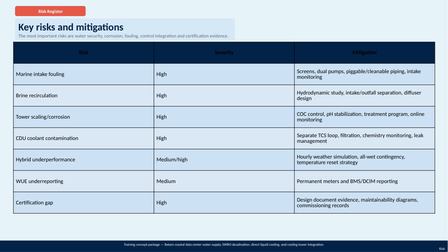The risk of coolant contamination in the cooling distribution units is similarly high, so we designed a separate cooling loop with filtration and chemical monitoring, along with leak management protocols, to keep the system clean and reliable. Hybrid system underperformance carries a medium to high risk, so we're using hourly weather simulations, developing contingency plans for all wet scenarios, and employing a temperature reset strategy to optimize performance.